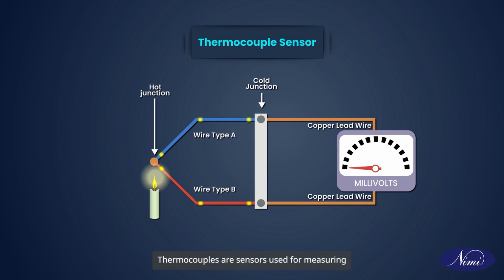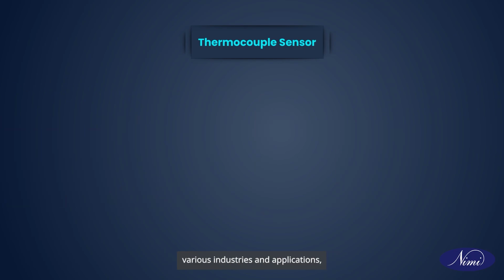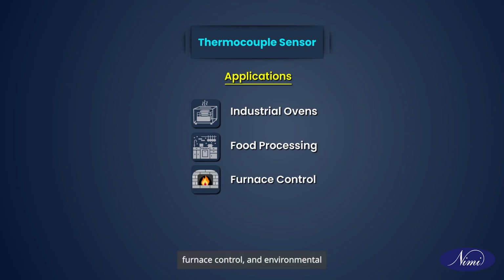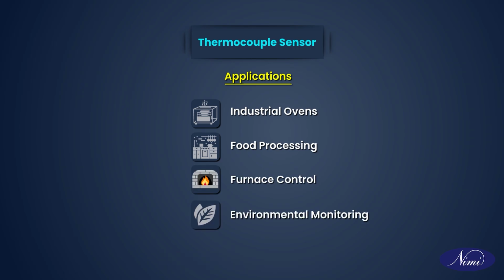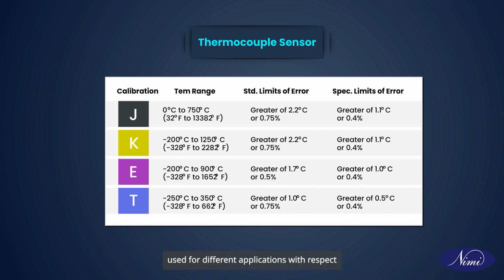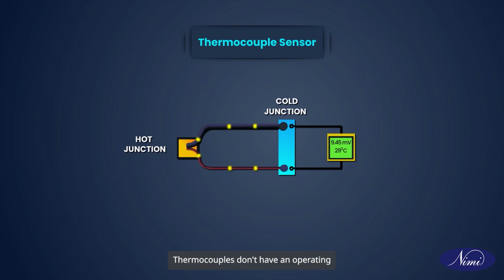Thermocouples are sensors used for measuring temperature based on the principle of the thermoelectric effect. Thermocouples are widely utilized across various industries and applications, including industrial ovens, food processing, furnace control, and environmental monitoring. There are different types of thermocouples used for different applications with respect to voltage and temperature. Thermocouples don't have an operating voltage themselves. They generate a small voltage output based on the temperature difference between the hot and cold junctions.